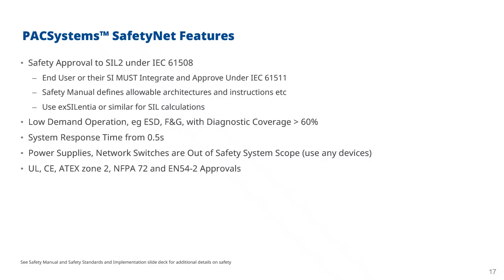Typically what you do is to actually do the SIL calculations. For that, you would use a piece of specialized software, and the reason is that when you're implementing a safety instrumented system, it's the complete system that has to be approved. It's no good just approving the PLC part. You also have to approve the input, the actuator, and the outputs. All of those also need to be safety approved, and in our case, also the field terminal assemblies. So there are software packages available for that. exSILentia is one, and that includes the PFD and the other figures, and that allows you to perform those SIL calculations. And then the output from that can be part of your documentation that your system meets the required safety level.